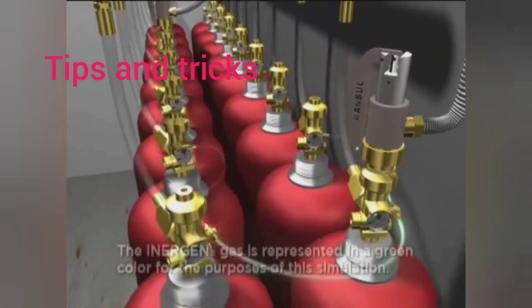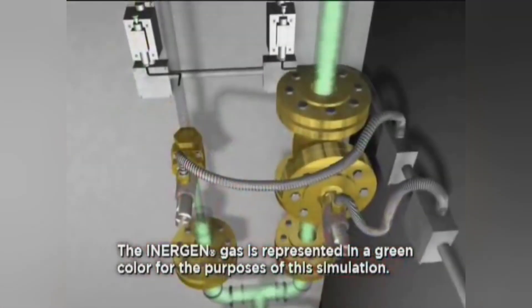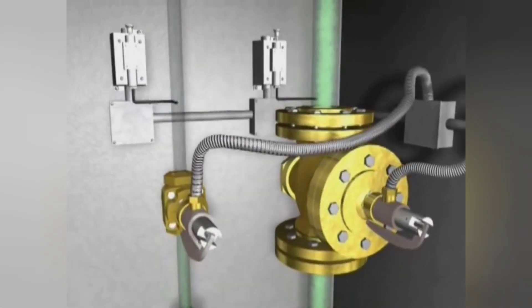The cylinder valve opens, allowing the Inergen agent to discharge from the storage cylinders. In places where Inergen is protecting more than one room, a unique selector valve is used to direct the system discharge into the appropriate zone.